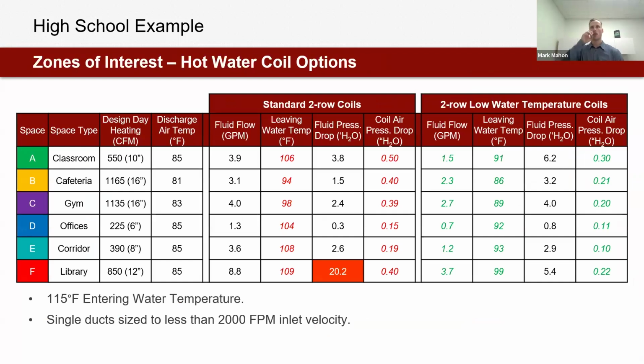And so once again, a review of these zones of interest. Looking at a standard 2-row coil versus the new 2-row low water temperature coil, we can see some significant differences in performance. In this case, the leaving water temperature for a standard 2-row coil is much higher than the leaving water temperature out of the coils for the low water temp coil.